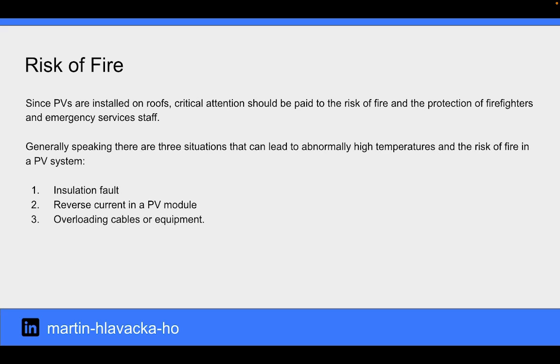And since PVs can be installed on roofs, critical attention should be paid to the risk of fire and the protection of firefighters and emergency services staff. Generally speaking, there are three situations that can lead to abnormally high temperatures and the risk of fire in a PV system: insulation fault, a reverse current in a PV module, and overloading cables or equipment.